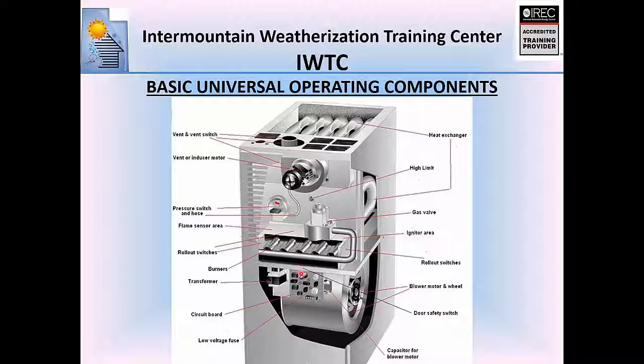I can't tell you how many service calls I've been on over the years because somebody changed their filter and didn't get the door back on right and didn't fully engage the door safety switch. So if the furnace isn't running, that's one of the first things I check. Did they get the door back on right? You get that call, "Oh, I just changed my filter and now all of a sudden the furnace won't run." Bet you the door's not on right.